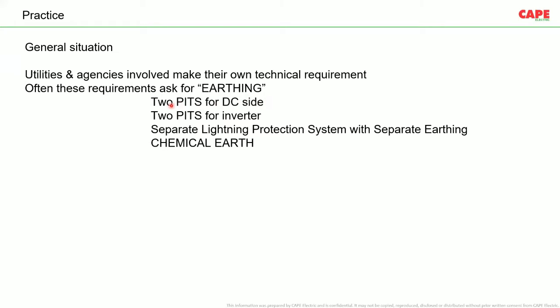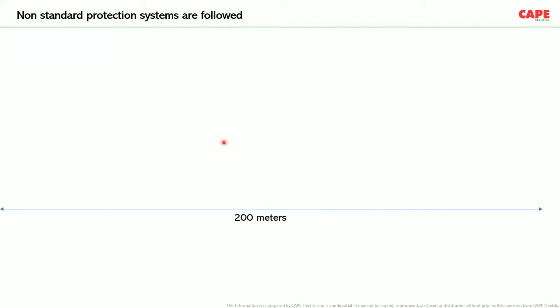So in a lot of cases, two earth pits are used for the DC side, two earth pits for the AC side, or for the inverter it is requested, separate lightning protection is requested, sometimes chemical earths are requested. Normally, these requirements from some of the agents, I'm not saying all the agents, are messing up the technical requirements. Because of this mess up, a lot of safety hazards are happening within the country. So please note that these requirements are not at all included.